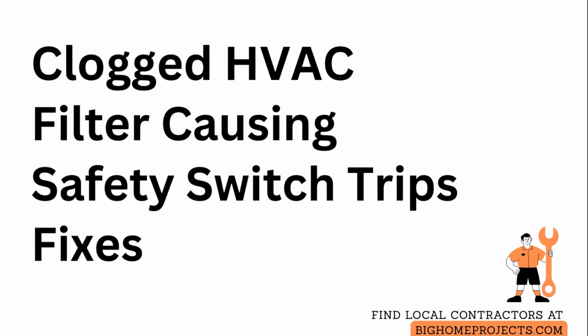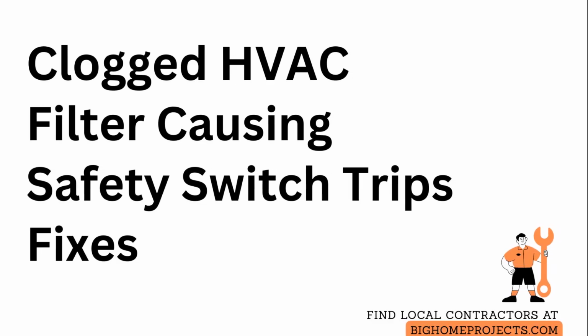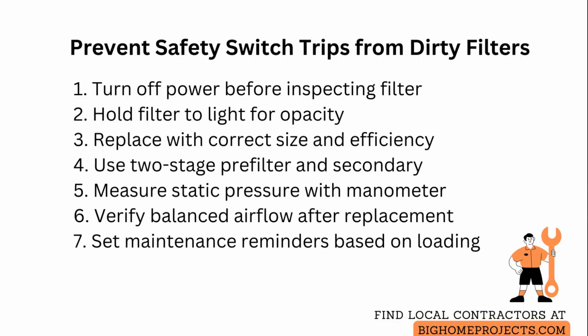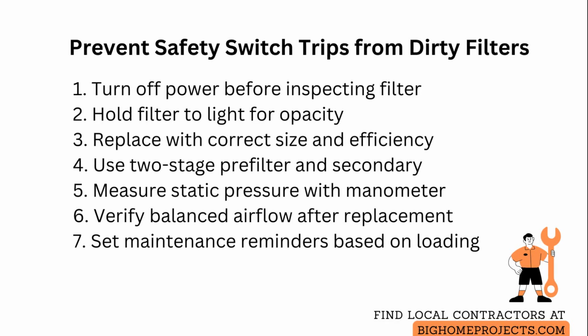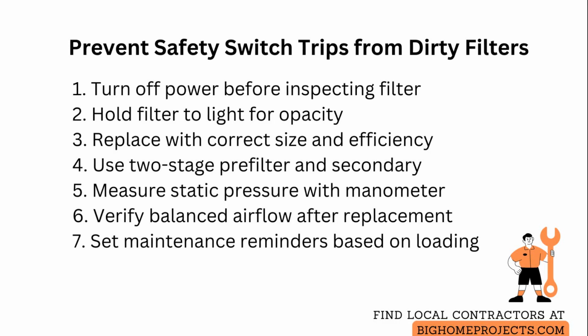Can dirty system air filters cause a safety switch to trip and shut down equipment? Clogged filters restrict airflow and cause motors, compressors, and heat exchangers to run hotter than designed, which can trigger temperature or pressure safety switches to open.